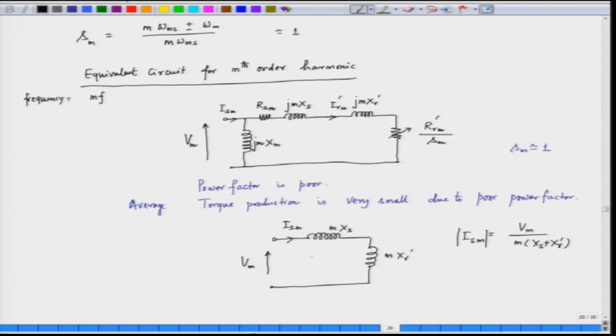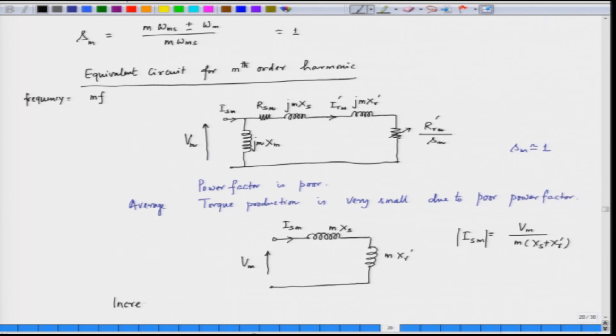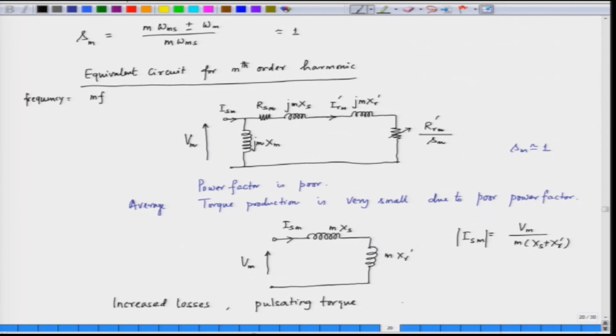There will be some current present. The effect of the harmonics is to increase the losses of the system. The losses are increased, and in addition to that there will be torque pulsation because the rotating fields of various orders will interact with each other to produce pulsating torque. The average torque production is very small due to poor power factor. The harmonics do not contribute to any significant average torque.